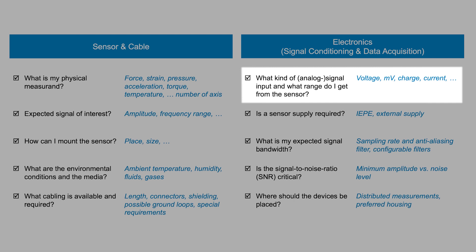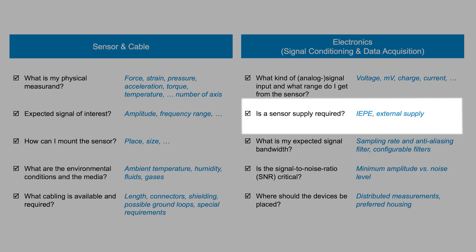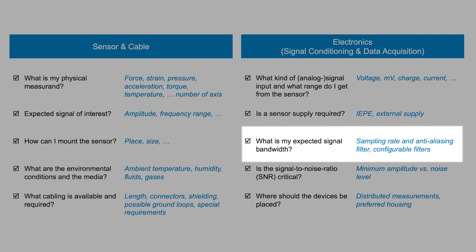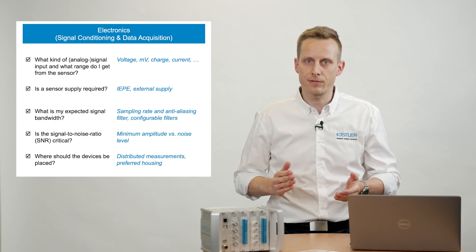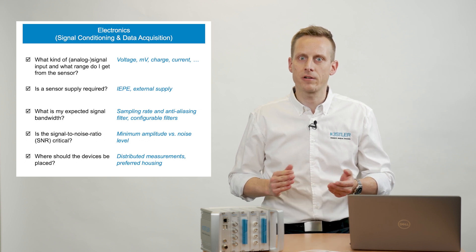On the electronic side: what is the electrical signal from the sensor, and what is the range? Do I need special amplification, like for strain gauges or piezoelectric sensors? Is it an active sensor which needs powering — for example IEPE sensors or piezo-resistive transmitters? Depending on the expected signal bandwidth, which sampling rate makes sense? Higher is better, yes, but it also creates a lot of data — therefore, select a feasible value for your application.